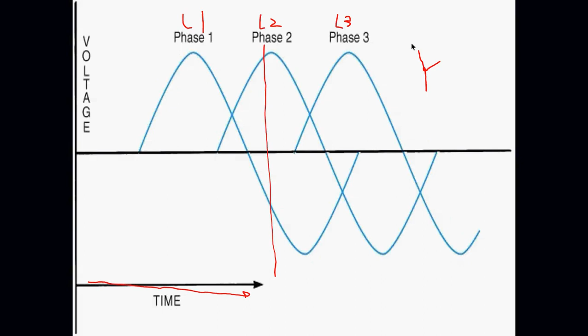Now we're going to go much deeper into three-phase motors, but there's a couple things I want to tell you. They have three hot legs, L1, L2, and L3. They all have the same resistance. We do not have a start and a run winding. Each leg of a three-phase motor will have identical resistance.